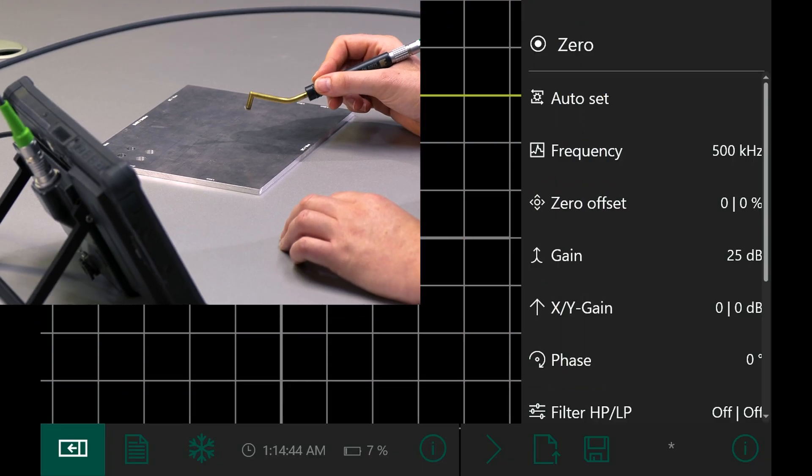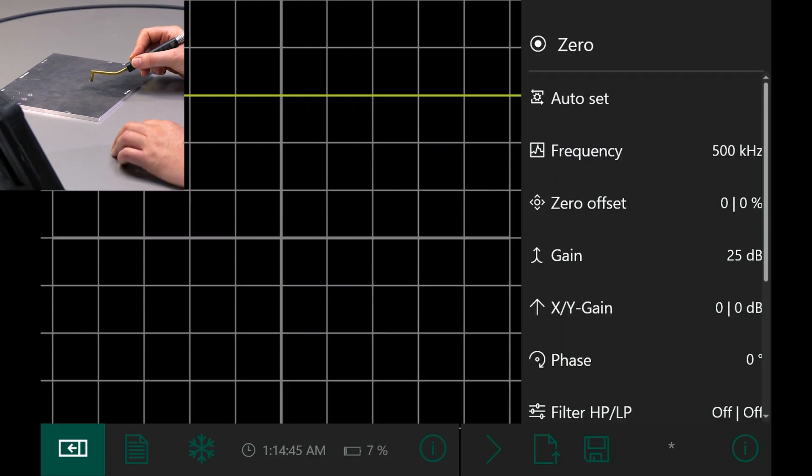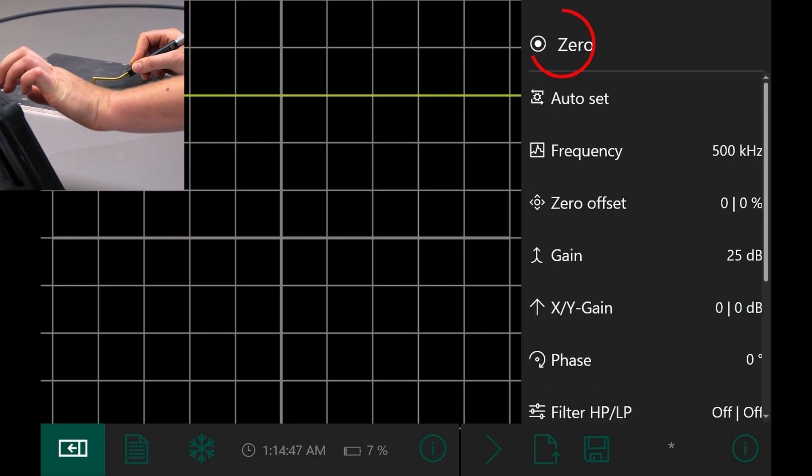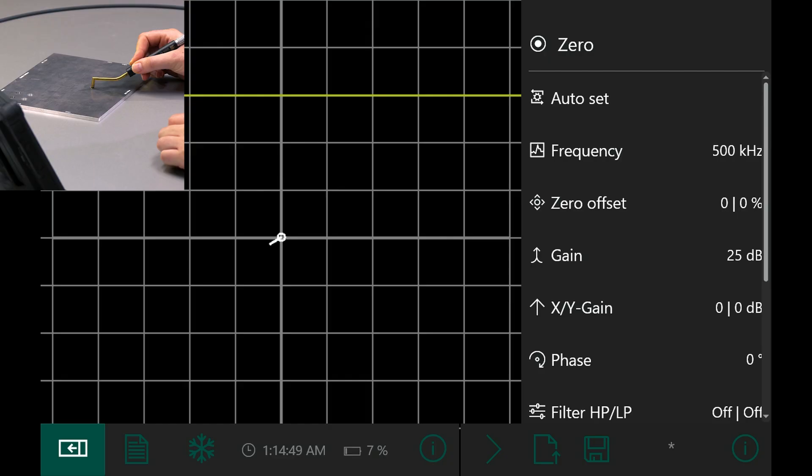I place the probe on a fault-free area of the test object and press zero. When the probe lifts off, the liftoff is visible.